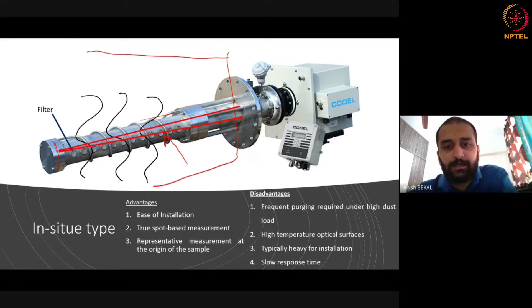Whereas the disadvantage is when you have a high dust load, these filters get choked quite often, and you need very high purging. Purging means basically sending high pressure air through these filters and removing all the dust on them. Also, you need very high temperature optical surfaces. If it is 80-90 degrees centigrade, we are fine, but there are applications where temperatures can go as high as 300 degrees centigrade. Then you need these mirrors or optical surfaces to be able to withstand temperatures of 300 to 500 degrees centigrade. Typically very heavy for installation. Its response time is not as good as a cross duct sensor, because the gas has to diffuse through these filters, and that diffusion can be pretty slow. So you have a very slow response time.